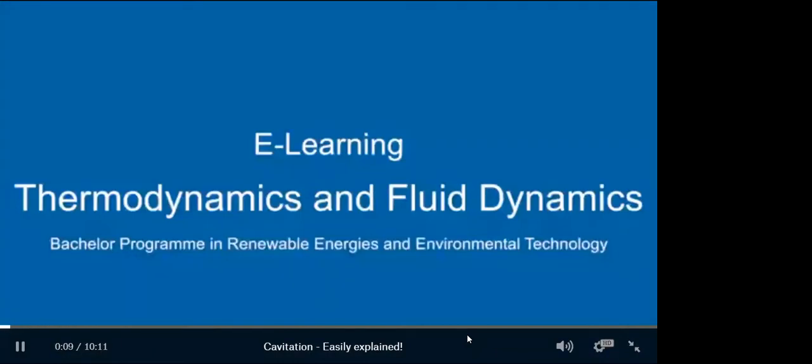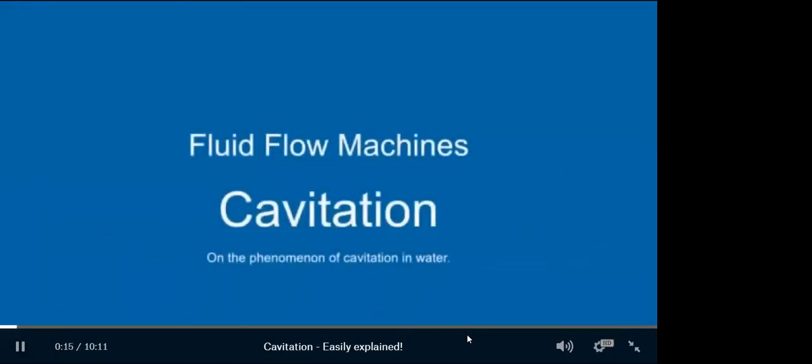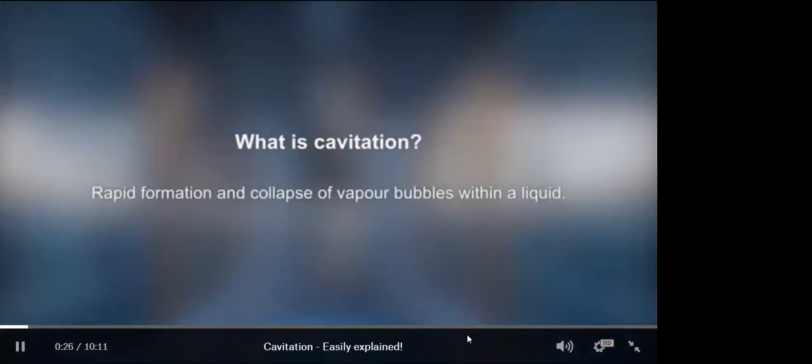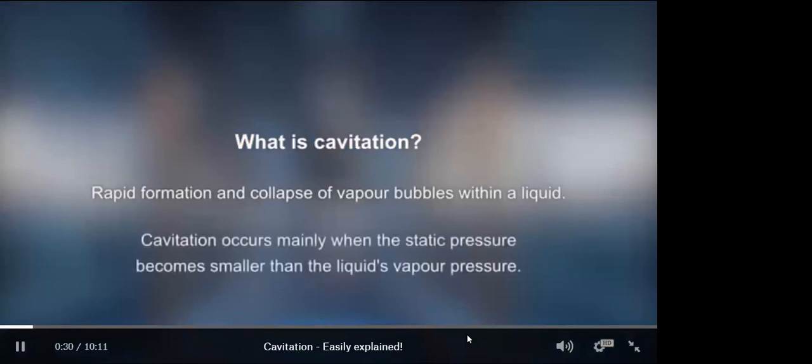Welcome to e-learning in thermodynamics and fluid dynamics of our bachelor program in renewable energies and environmental technology. In this series, we are going over the phenomenon of cavitation in water and its consequences. What is cavitation? Cavitation is the rapid formation and collapse of vapor bubbles within a liquid. Such cavitation bubbles are formed mainly in locations within the liquid where the static pressure becomes smaller than a liquid's vapor pressure.